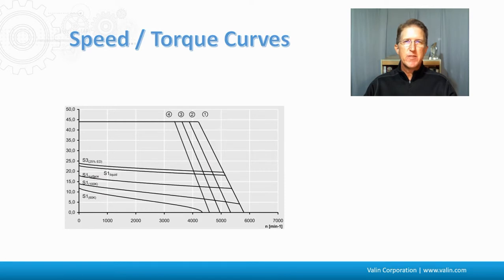If we take a look at this speed torque curve here that is far more detailed, you can see the different voltage curves that we get. So different voltages give us different speed capabilities. This may be 200 volts AC, maybe this is 208, 230, 240, something like that. If this is 240 here, then there's going to be a 120 curve here. Now, if you remember the way the drive works, 120 volts AC is rectified to 170 volts DC. So 240 volts AC gets rectified to 340 volts DC. So these curves don't necessarily equate the AC power that you're looking at. You've got to rectify it up to the DC voltage.